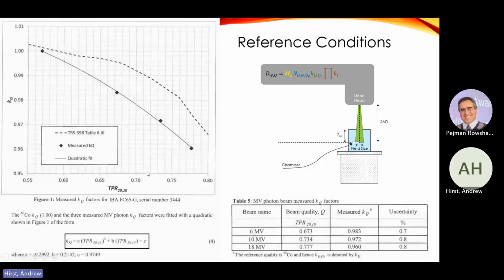What we will then do is use our chamber in our beam with our own qualities. And yeah, we have 6 MV and 10 MV, but it's not the exact same in terms of the entire spectrum. That's your nominal energy, but no 2 beams are the same. So we will then take a measurement of TPR 20,10 in our beam with that chamber, plug it into here, and get our own KQ, or our own correction for beam quality.